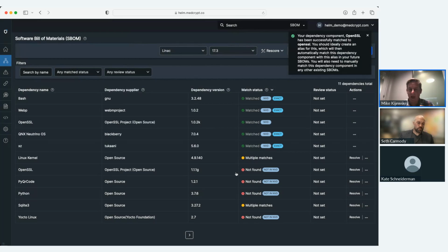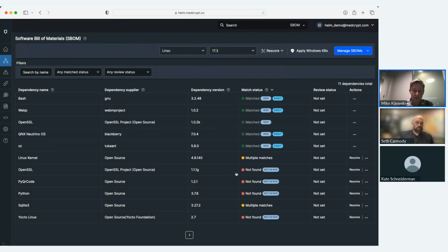That's great. As part of the analysis, when you're first releasing this product and analyzing the SBOM, you really need to go through the majority of these components and figure out, am I not finding a match in the NVD because there isn't one, to our point earlier, or am I not finding a match in the NVD because the data that I've put in doesn't match with what's in the NVD? And it's really common for the data in the SBOM to be close, but not exactly what's in the NVD. So you definitely got to look for that particular use case there. There's some amount of analysis that's required, either again manually or through some automated process, to match what you have in your SBOM to the NVD.